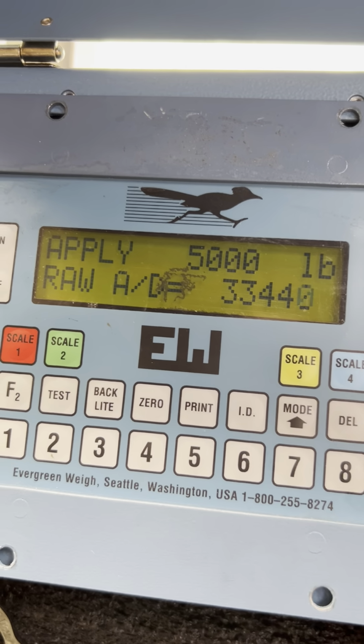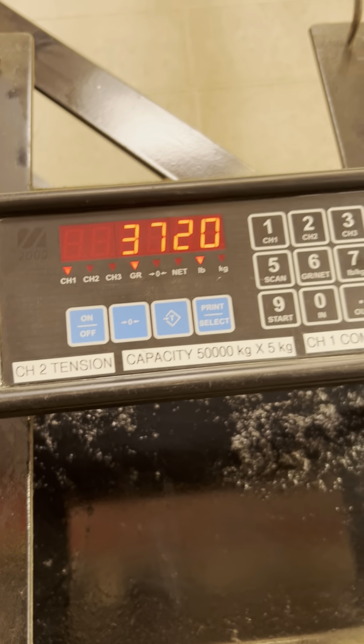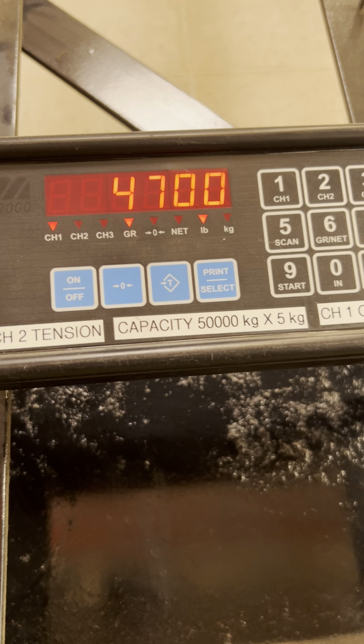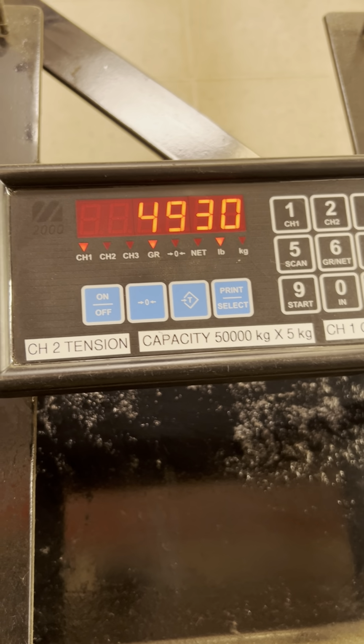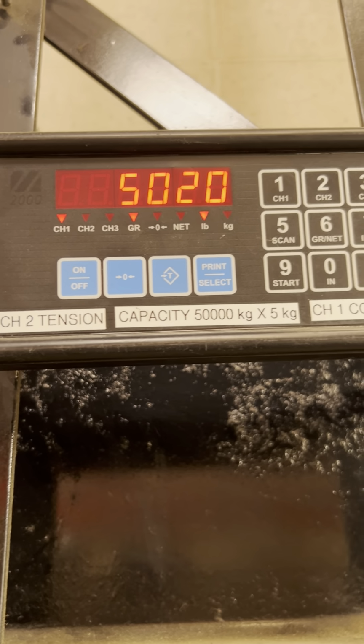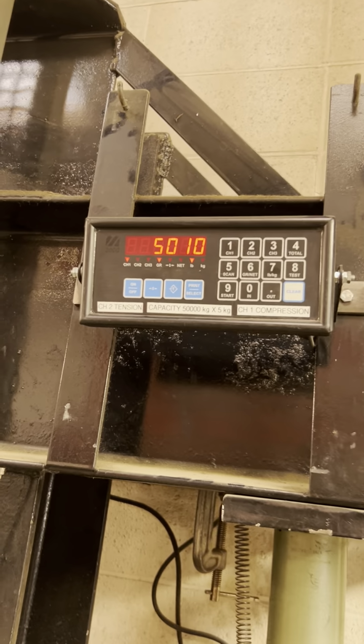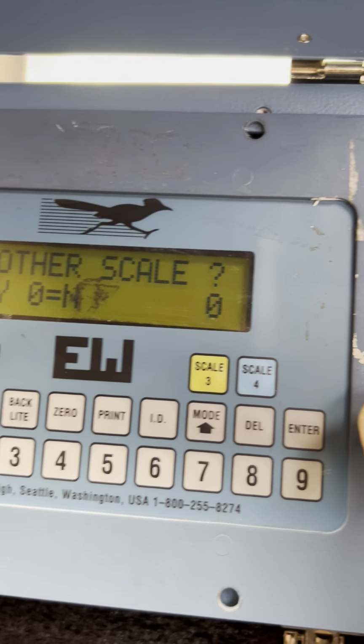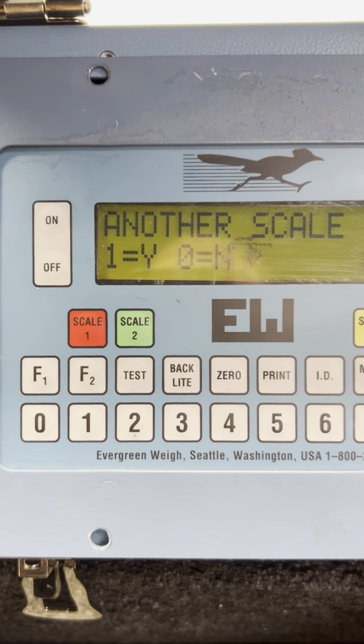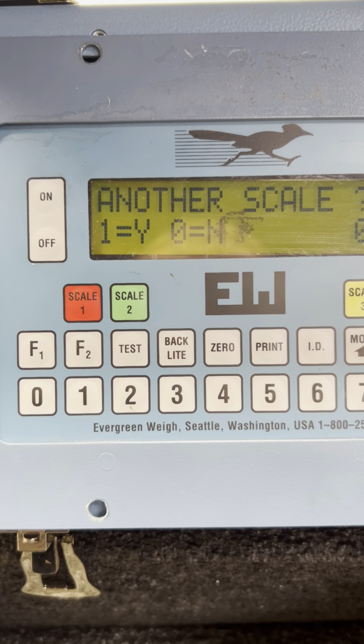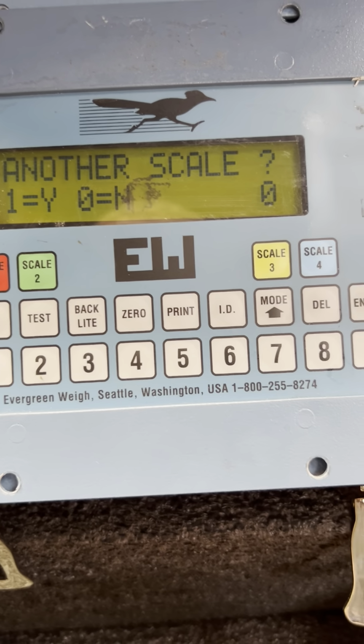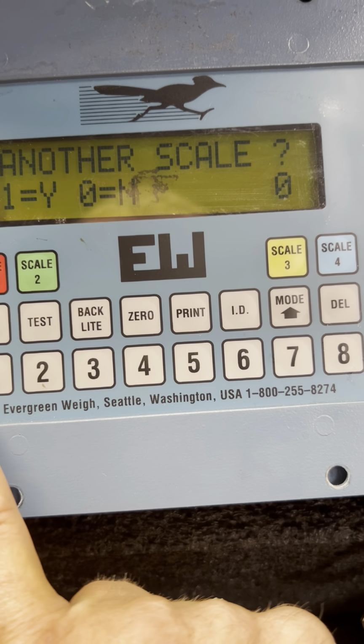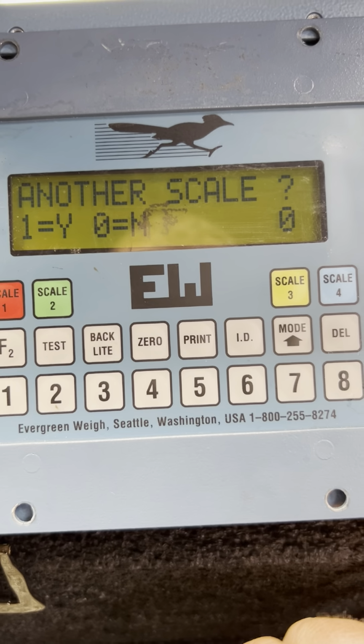Now it's asking about 5,000 pounds, so we have to put 5,000. It shows 5010. We're waiting until it will be 5000 and press enter. And now we just calibrated it, and it's asking us about another scales. No, we don't need to calibrate another one. So we press 0 and the enter button.